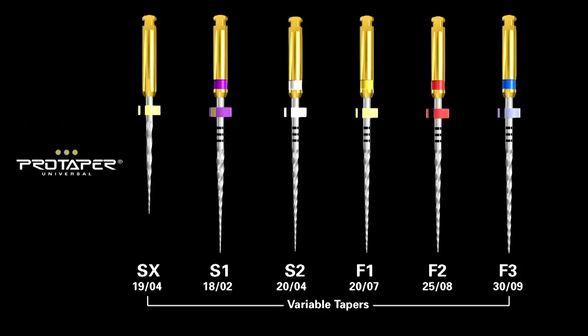Now that we have a glide path, let's discuss the files we'll use for shaping this canal. I'm going to show you the ProTaper system. ProTaper came to market in 2001 and is the most utilized system in the world. There are three shaping files and three finishing files — and note there's actually an F4 and an F5, but today we're showing what is most generally utilized. Notice specifically: variable tapers. This is the first system in the world to introduce progressive tapers over the active portion of a single file.